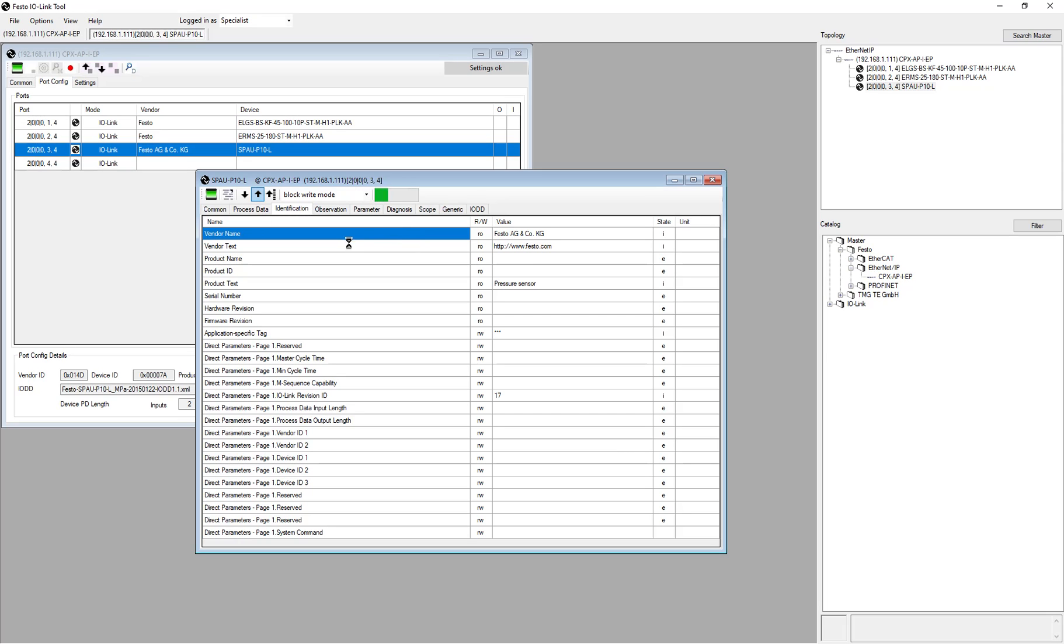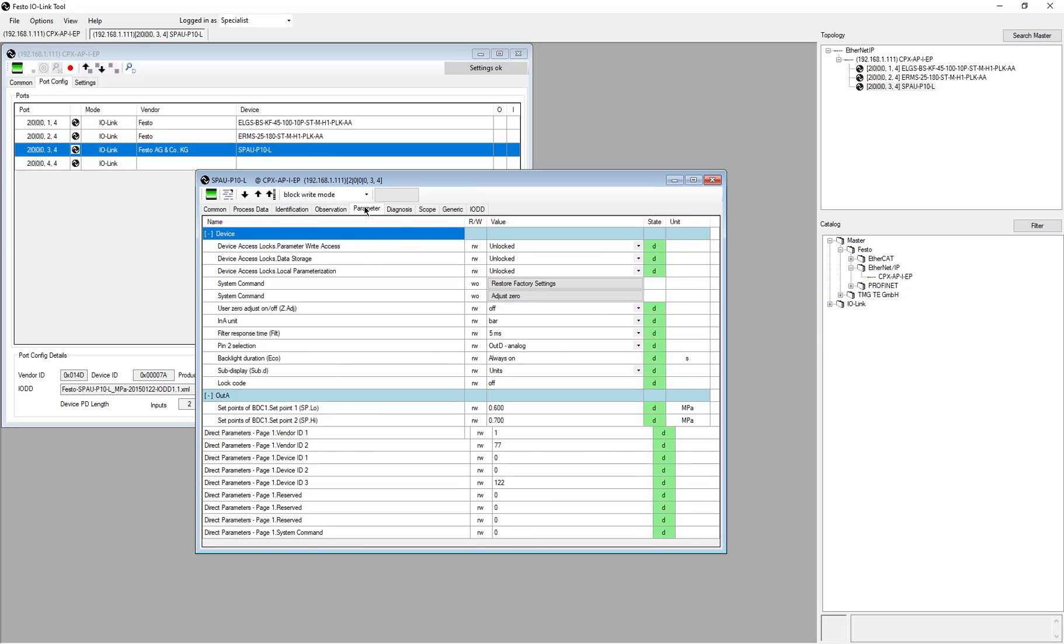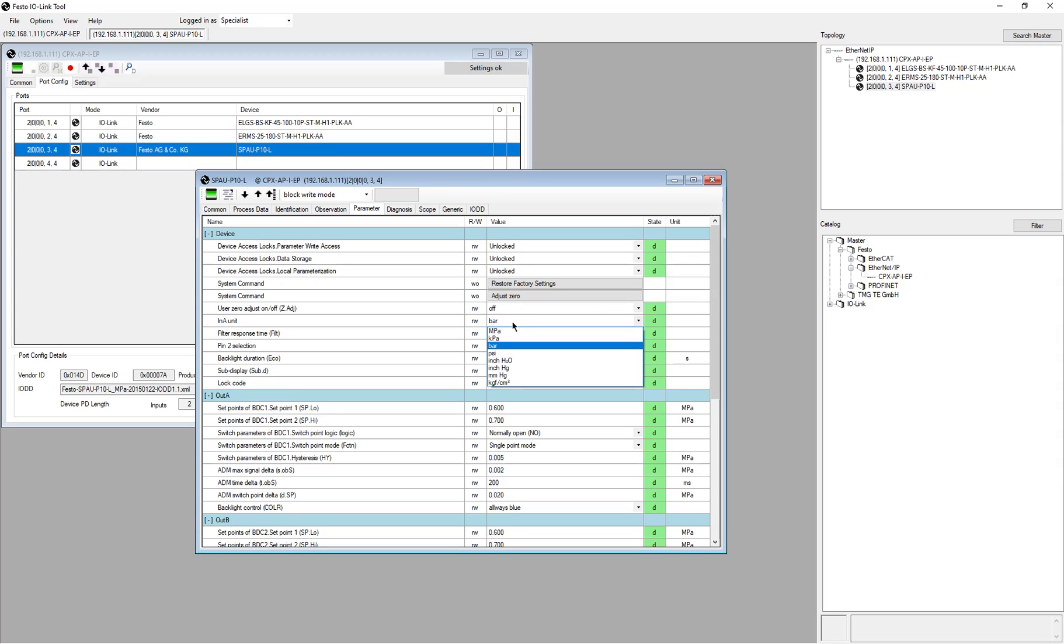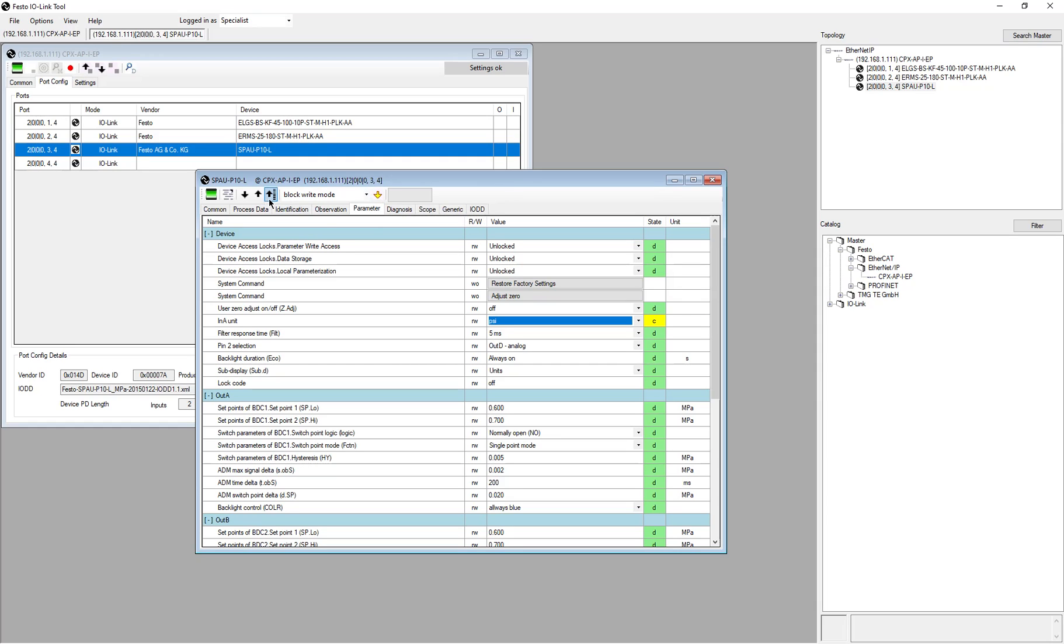If you want to make a download or modify something, let's say we want to change from bar to PSI, you see here it says change is edited, and then you do a block write, or you can do a download to the device, and then it should say that you're synced again.